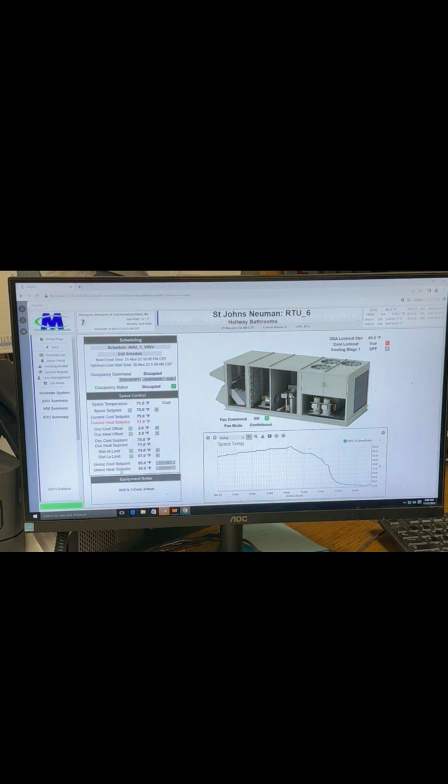If you look, you want to change these, especially if we have individual schedules. Our unoccupied heat is at 55 degrees, so it's cranking it up all the time. Well, no, it's going to let that space get down to 55. They won't sit around very long at night, that's for sure. But that's just for this zone. You can increase it. What would you put it at? 65. Yeah, we'll change it then. Let's just do it. There you go. 65 on the unoccupied heat, and I would go 78 on the cool. Okay.